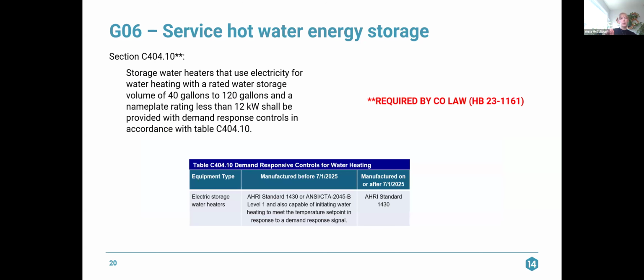So section C404.10 is the requirement that electric storage water heaters between 40 gallons and 120 gallons and a nameplate rating of less than 12 kW be provided with demand response controls. This section is written into the Model Low Energy and Carbon Code. It is not in the 2024 IECC. It is also required by Colorado law. So even if this doesn't make it into someone's local jurisdiction's energy code, it is still required by law to have these demand response controls.